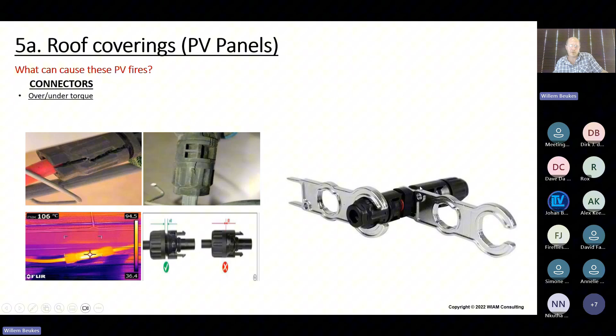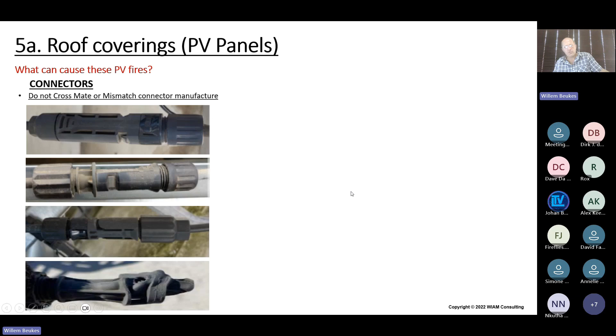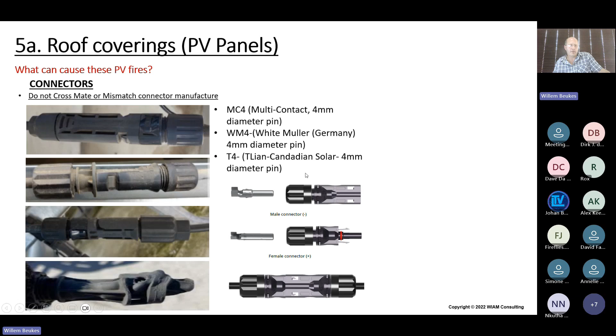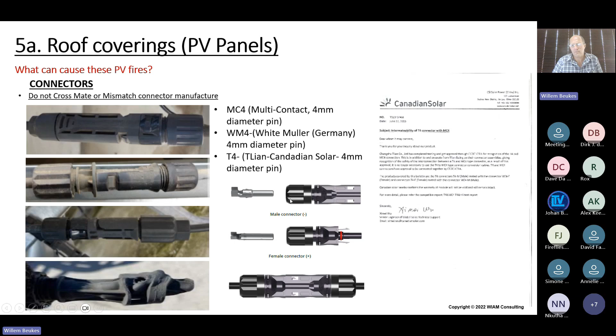In most cases, also you have mismatch of connector manufacturing. You have MC4, you have T4 connectors. So you have to have the same type of connector dependable on what comes with the panel to match those connectors. Otherwise, there will be a mismatch, and then due to the mismatch of these type of connectors, heat forms between that. We have the MC4, which is a multi-contact 4mm diameter pin. We have a WM4, which is a Weidmuller, mostly in Germany, and the T4, the T-line Canadian diameter pin. And they need to match, otherwise you have a mismatch in terms of the connectors forming arc. Some manufacturers provide solutions where a T4, for example, on an MC4 can be used, but it needs to be from the manufacturer to provide safe usage of that mismatch of the connectors.